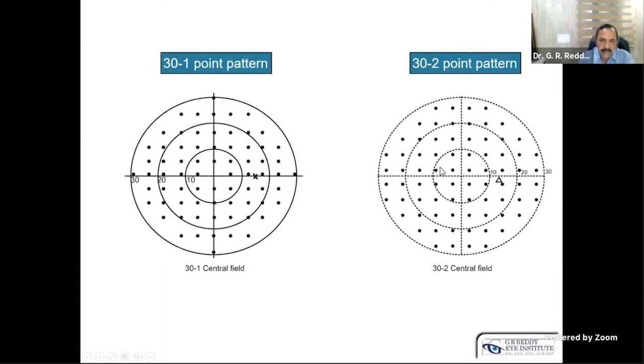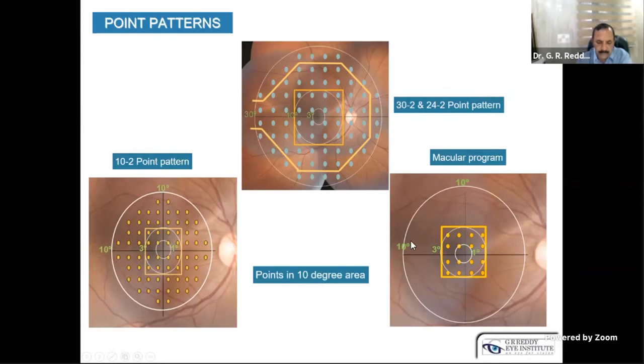In the point patterns that we use in glaucoma in the Humphrey field analyzer, we have 30-2, 24-2, 10-2, and the macular program. Whenever we talk about the point pattern, the minimum things we should know are how much area the points are distributed over, how many points there are, what the distance is between point to point, what the distance is between point and the axis, and what the bare area is. These are the points we should always look for, and the point patterns differ from machine to machine. Therefore, before buying any machine, have full control and concept over the point patterns of that particular machine.